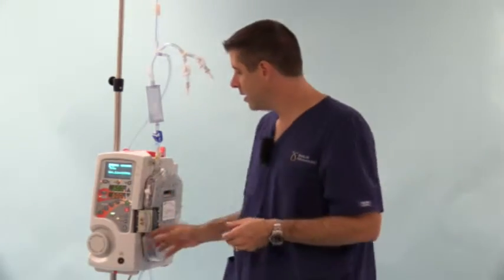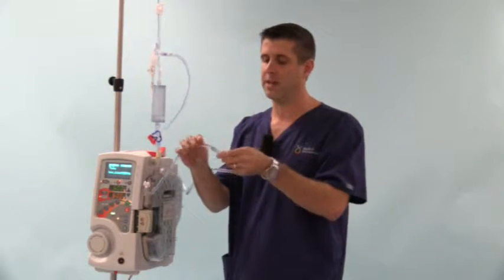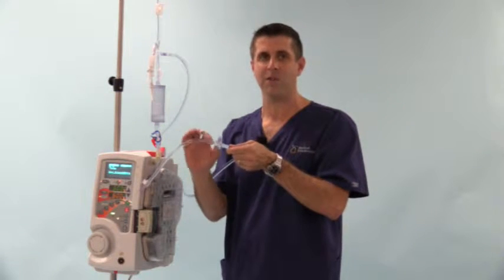However, due to the nature of warm fluids on any system, you may have some outgassing in the patient line. How you'll see that is small bubbles start to collect. That's due to the nature of having warm fluids in the patient line itself. We made it easy to remove those. We include a swabbable port on every patient line that allows you to tap the small bubbles as they collect into larger bubbles toward the swabbable port and simply remove them with a syringe.